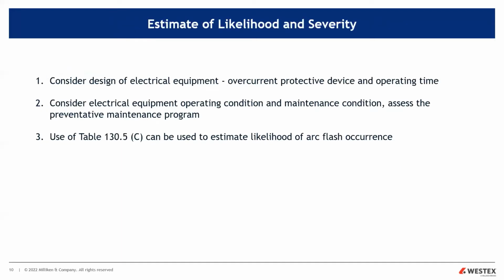So again, qualified personnel, consider the design of the equipment is key. Make sure you're looking at the overcurrent devices. The best rule of thumb to determine the likelihood of incident occurrence and severity of injury is really best if both a qualified safety professional and a qualified electrical engineer familiar with the electrical systems look at the equipment together to consider the design of the electrical equipment, the overcurrent device coordination, and determine the operating and maintenance condition of the equipment. If doing the incident energy analysis, of course, if you're doing that method, which is the more precise, more accurate method, if you will, the qualified electrical engineer was certainly going to be privy to the likelihood of occurrence on the equipment.